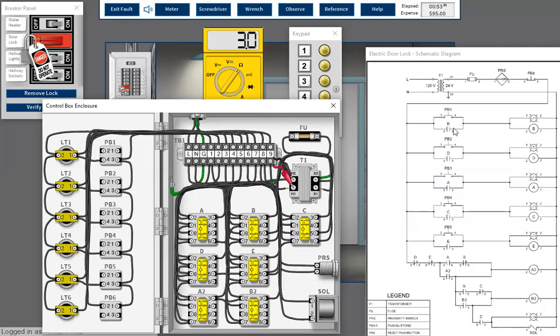I'm thinking of a control transformer that usually, you know, you've got about 15 ohms on the primary and about 7 or 8 on that secondary. But I guess they're working with a little bit different transformer. So just keep that in mind. This transformer is 3 on the primary and 0.5 on the secondary. If you remember, when we checked the secondary before I replaced it, it was like 40, I believe. So we got to be mindful of that.